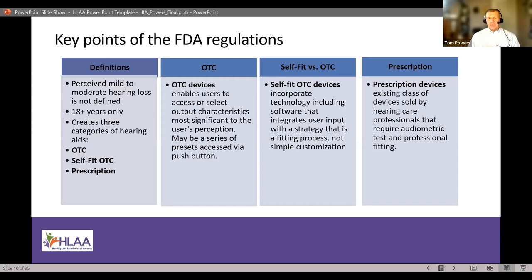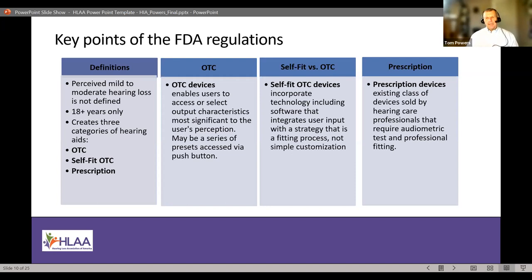There were three categories of devices put into the regulations. OTC is the broad category, but it's broken into two types: standard OTC and self-fit OTC. The third category is prescription — the devices currently in the market that most of us are familiar with, fit by hearing care professionals. OTC devices enable users to access or select output characteristics most significant to their perception — for example, a series of presets accessed via push button or some other simple way to change the device's characteristics.